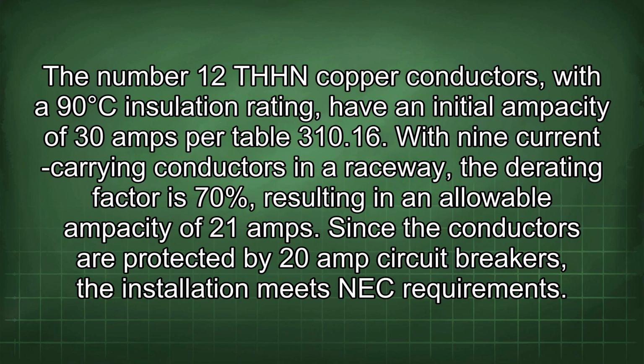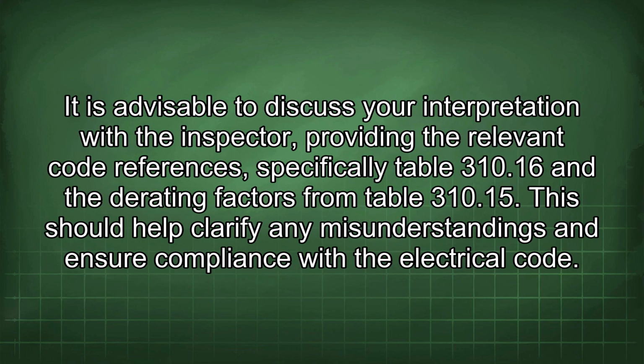The number 12 THHN copper conductors with the 90 degrees C insulation rating have an initial ampacity of 30 amps per Table 310.16. With 9 current-carrying conductors in a raceway, the derating factor is 70%, resulting in an allowable ampacity of 21 amps. Since the conductors are protected by 20 amp circuit breakers, the installation meets NEC requirements. It is advisable to discuss your interpretation with the inspector, providing the relevant code references, specifically Table 310.16 and the derating factors from Table 310.15. This should help clarify any misunderstandings and ensure compliance with the electrical code.